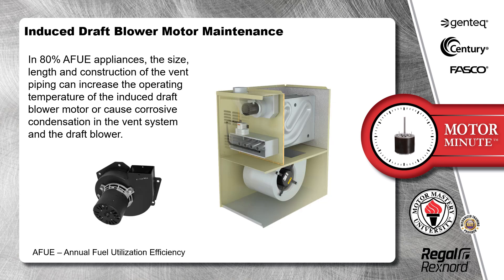In 80% AFUE appliances, the size, length, and construction of the vent piping can increase the operating temperature of the induced draft blower motor or cause corrosive condensation in the vent system and the draft blower.